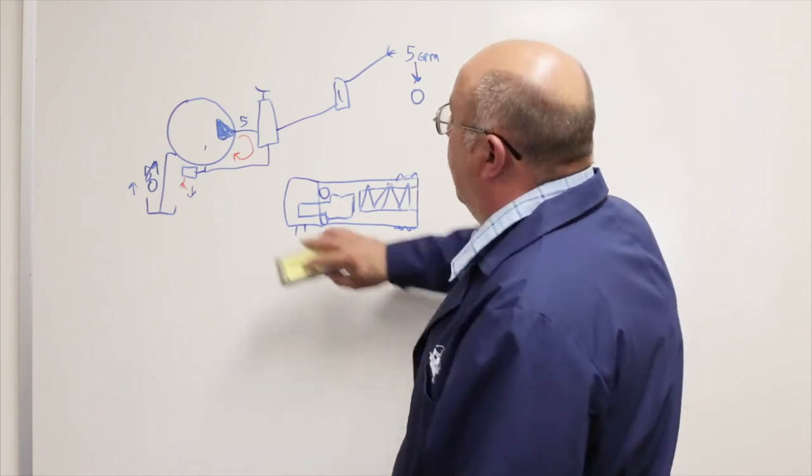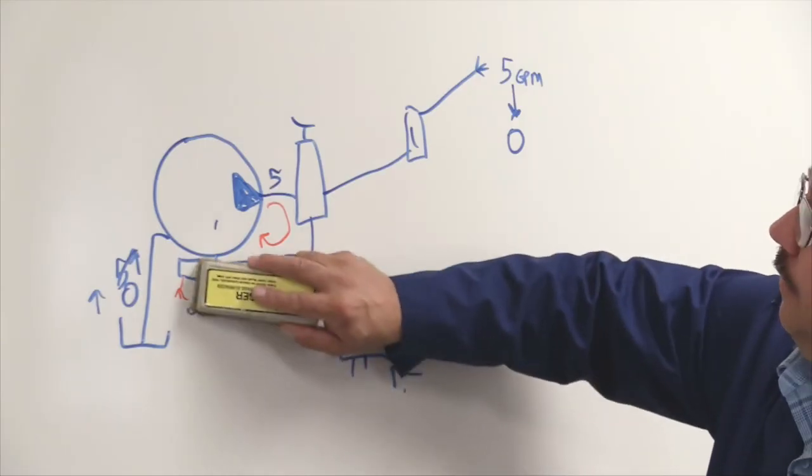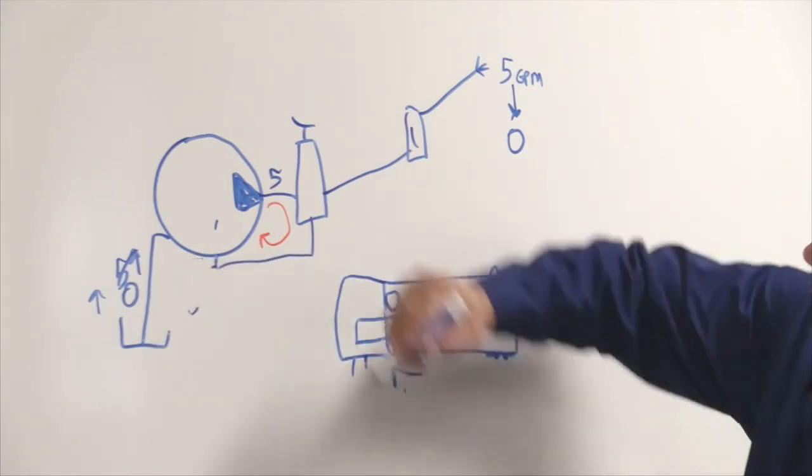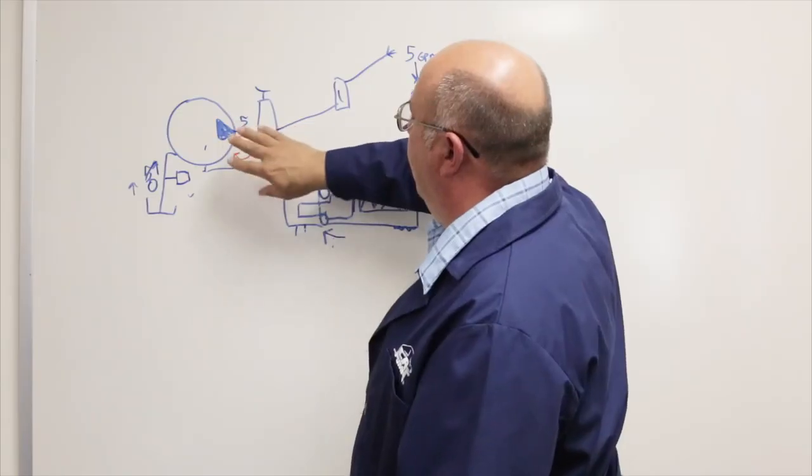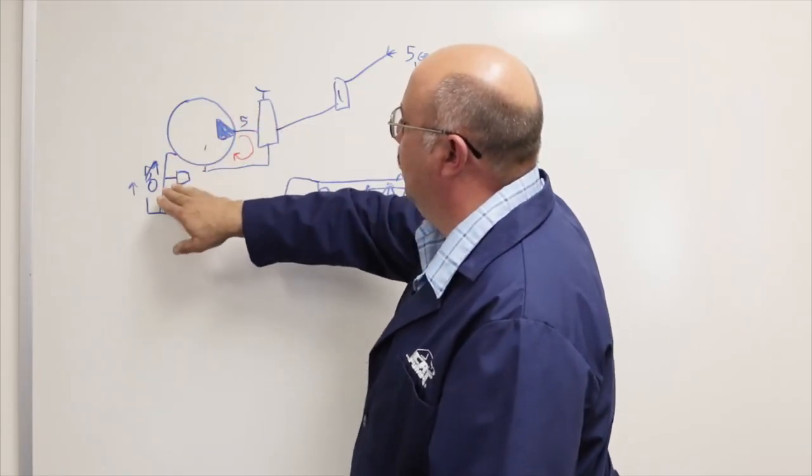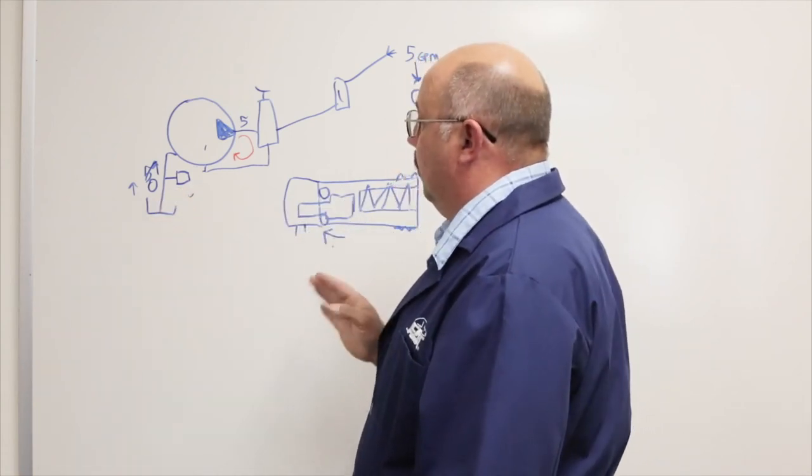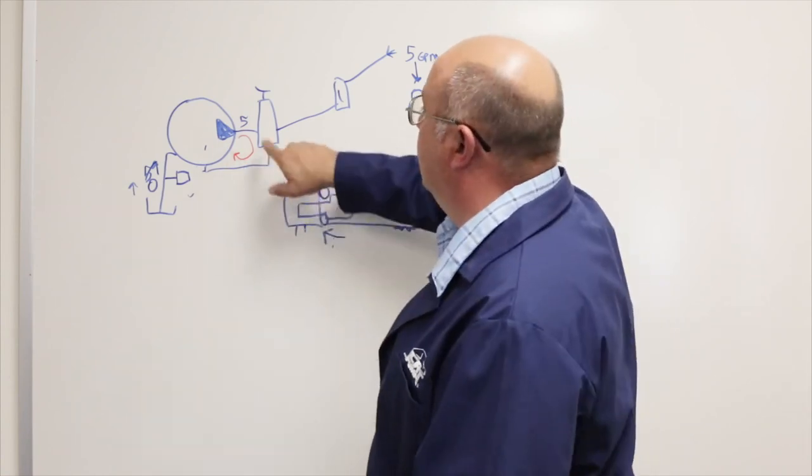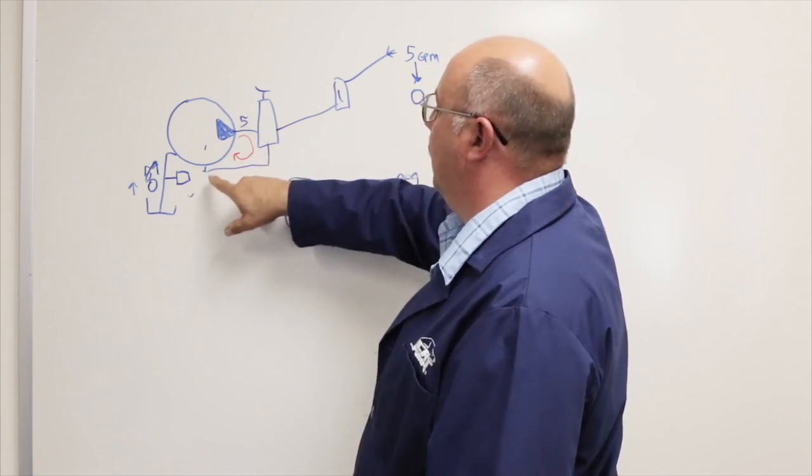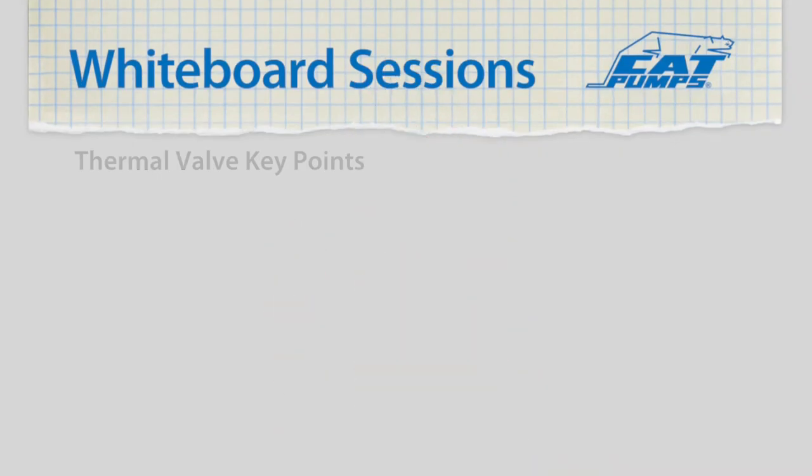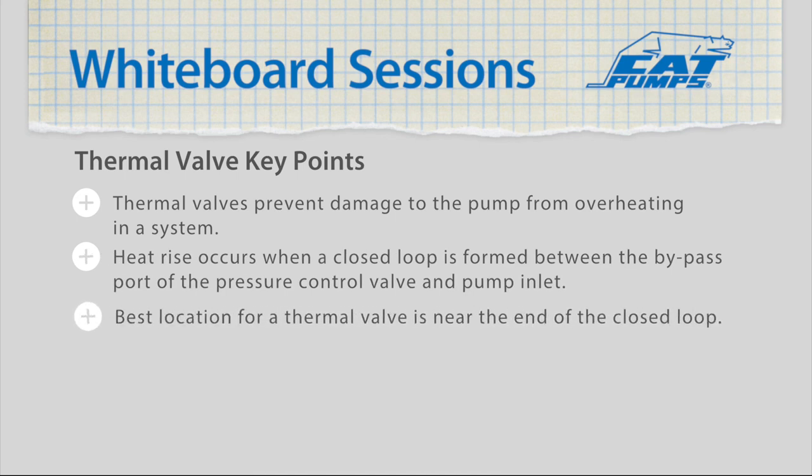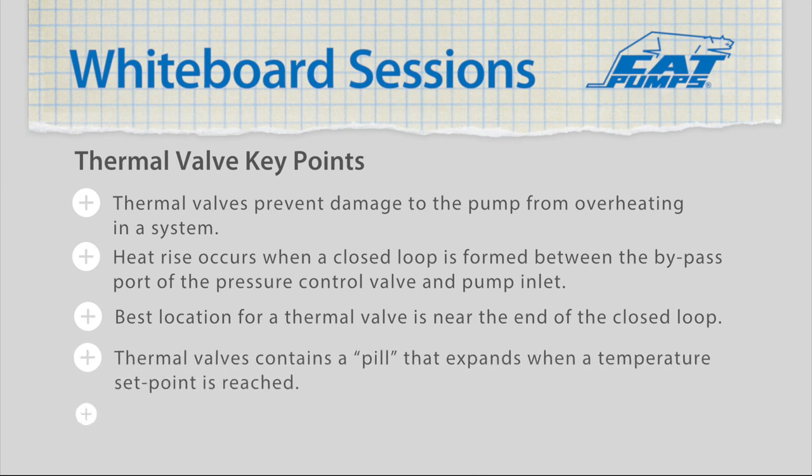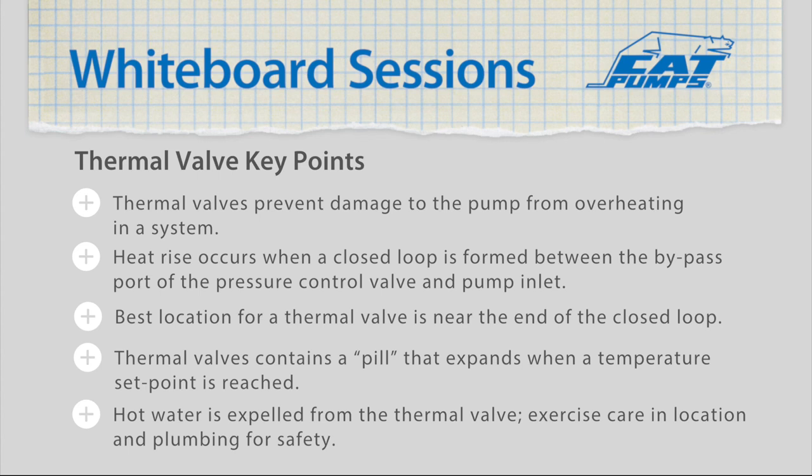Now, what we're also going to cover is where to mount this thermal valve. If I were to take it off of here, perhaps, and maybe mount it into my inlet line here, now when this water's in a loop, the temperature rise is still happening, but it's not getting to where the thermal valve is located. So we have to be very careful to mount the thermal valve in a position so it's going to see the temperature rise. Get it in this loop. Preferably as far at the end of the bypass loop as possible just before re-entering the pump.